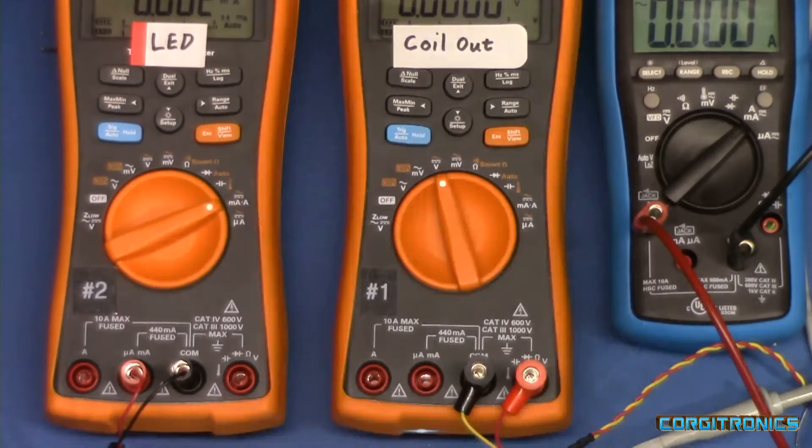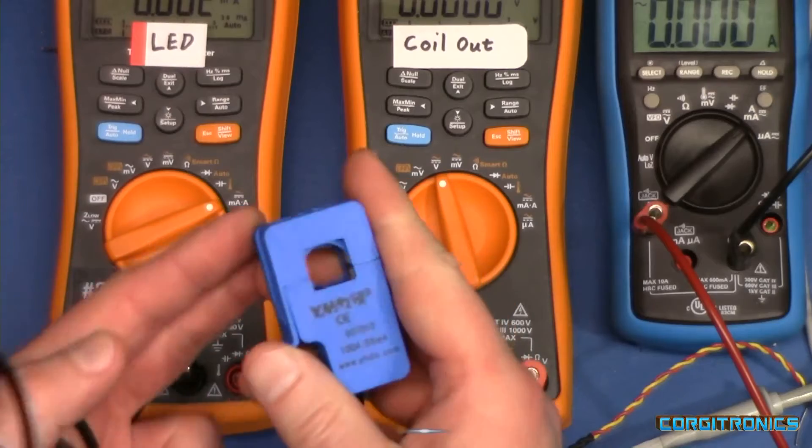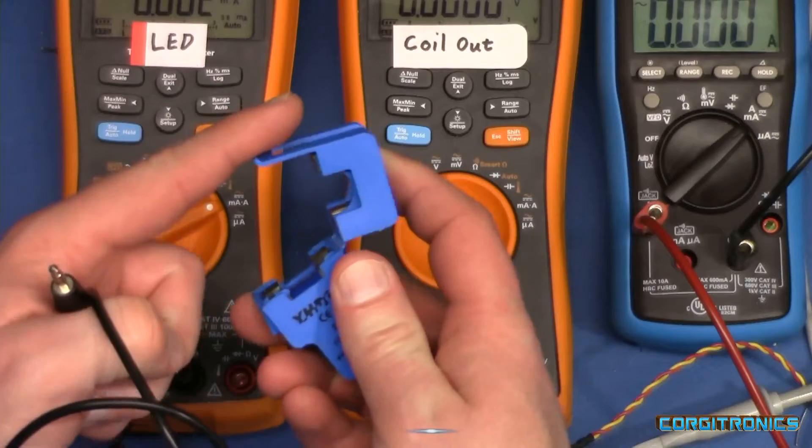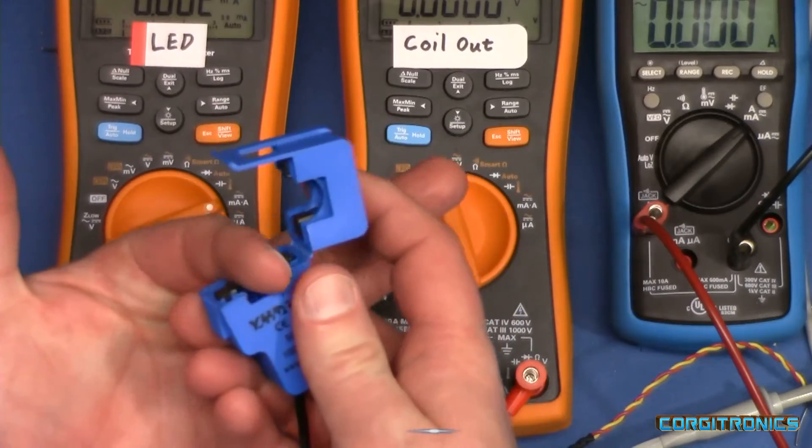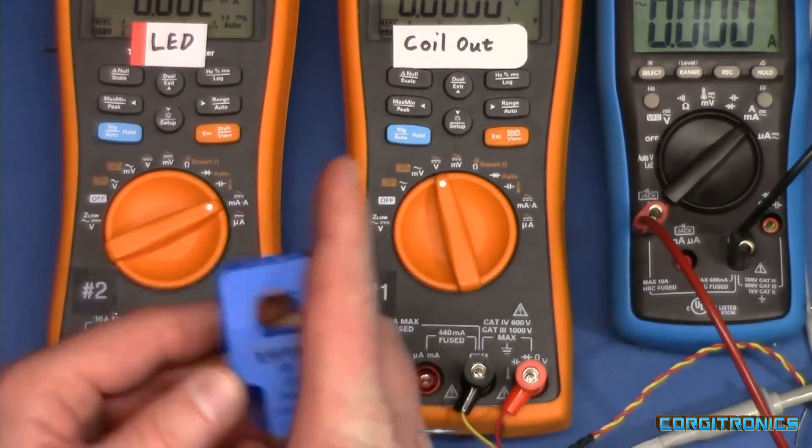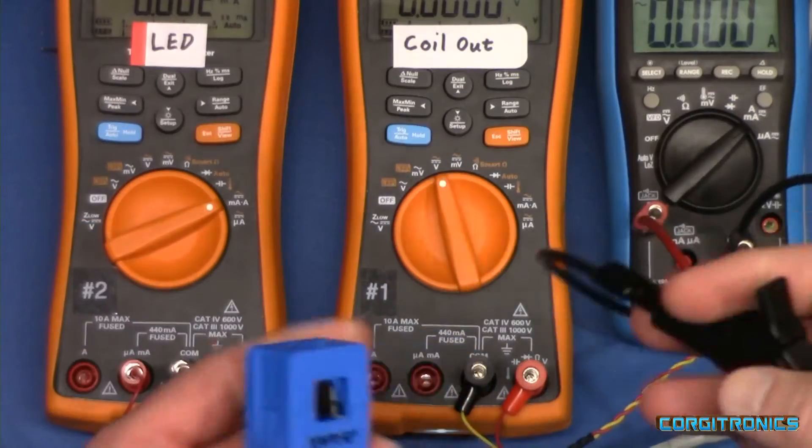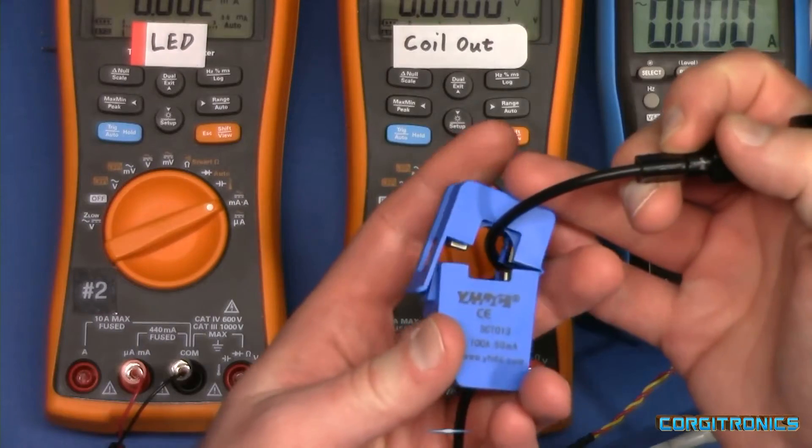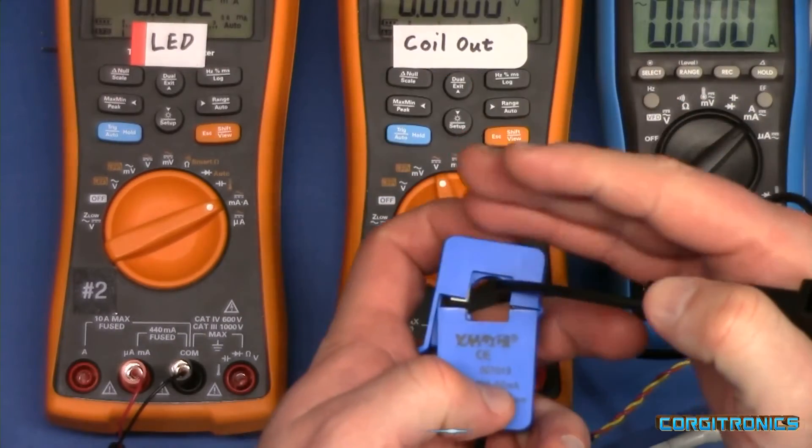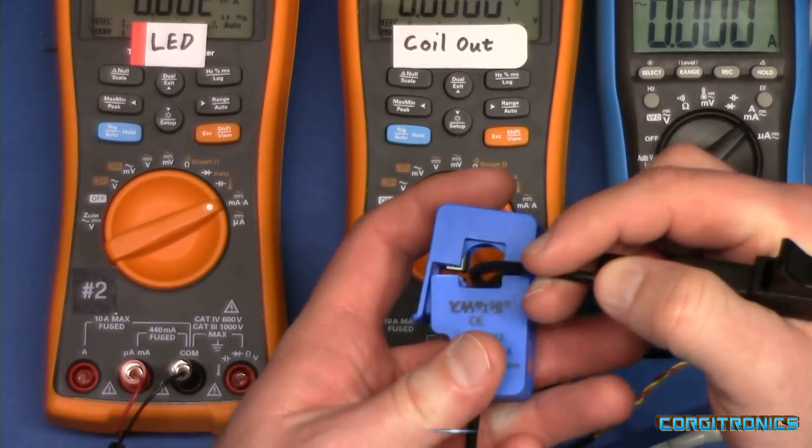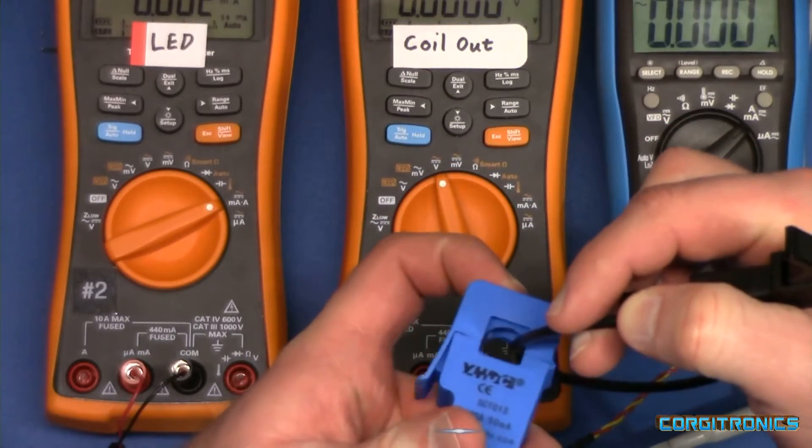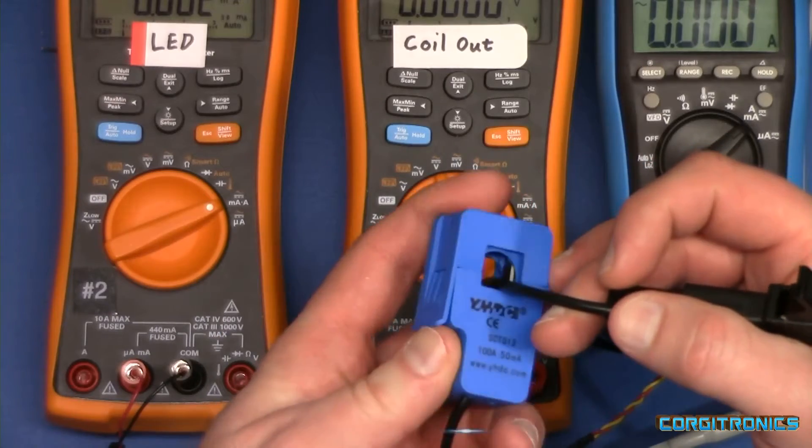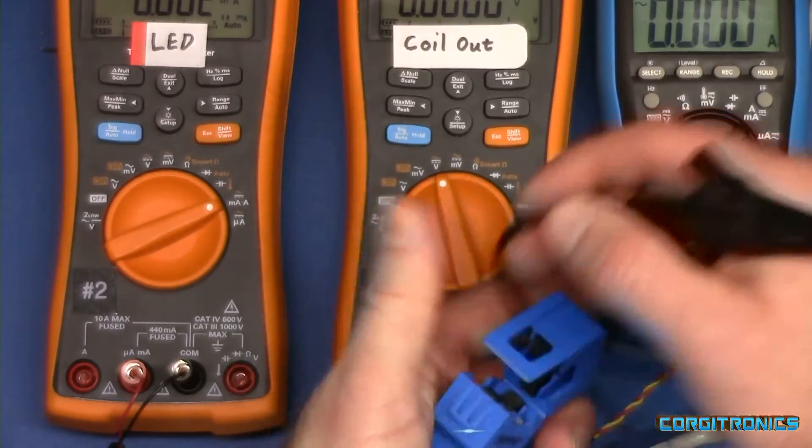However, a follow-up question came along about what's called a split core current transformer. It's named because the core opens up and you can put your wire through the middle and snap it down. The reason you would do that is if you could not cut your wire, you just need to split your hot neutral lines apart, and then you could slip this core transformer around it and hook it right up. It works great. They're used in a lot of places. Let's see if it'll work for this.